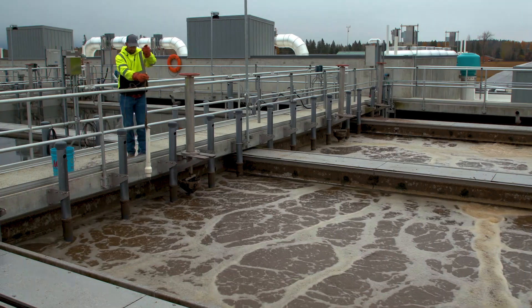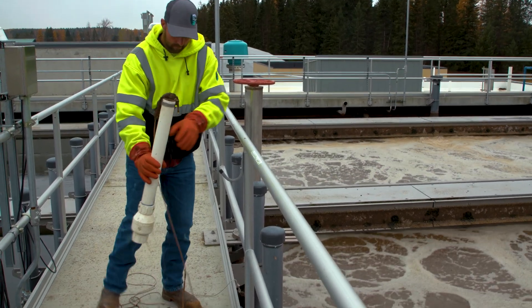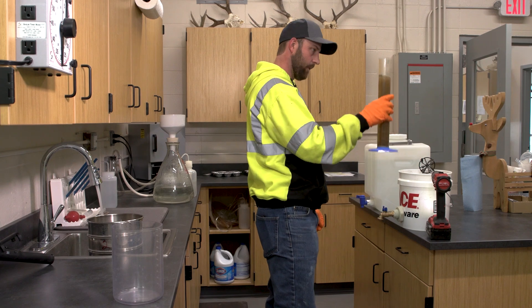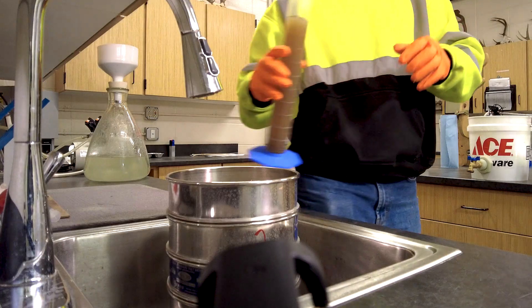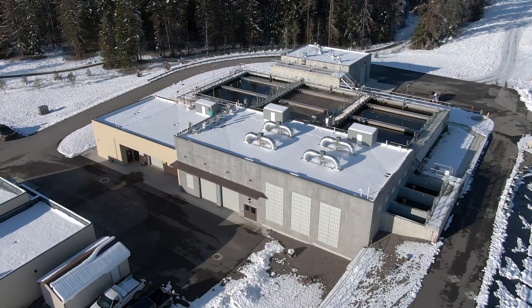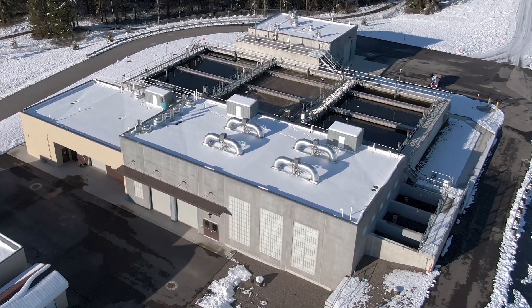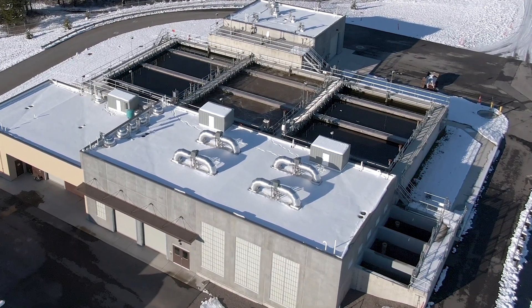The granular activated sludge we found to be very robust. We're able to handle many different kinds of incoming water — low nutrients one day, high nutrients the next — and the AquaNereda plant is doing great for us. Since the AquaNereda system went online about three years ago, we've been meeting our permit requirements and haven't had any issues with cold weather ammonia removal, which we struggled with previously.